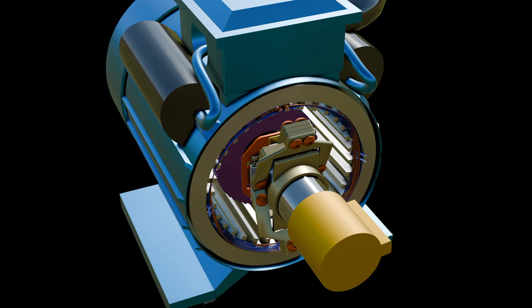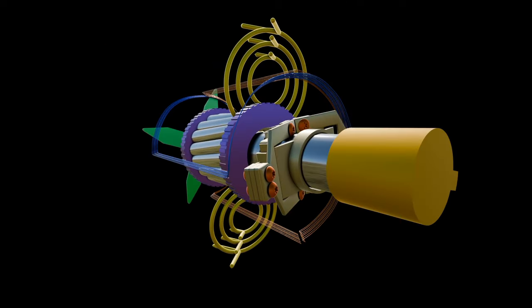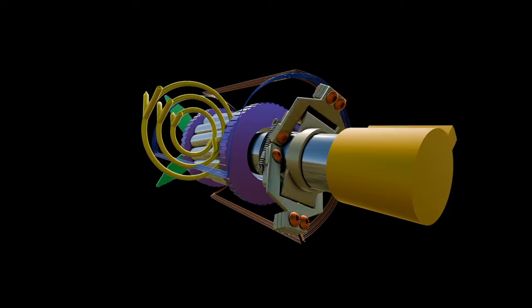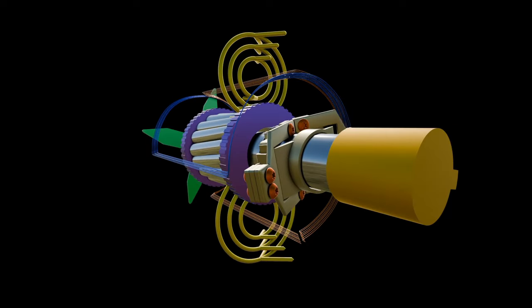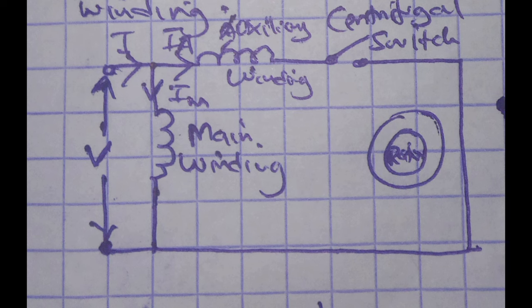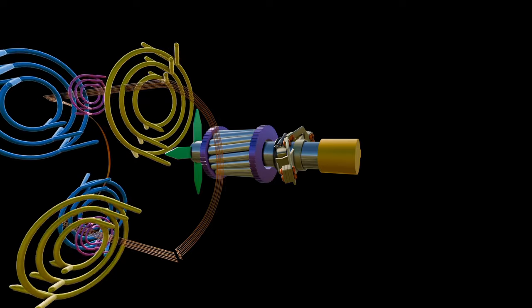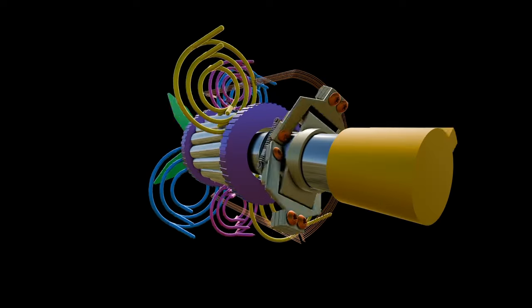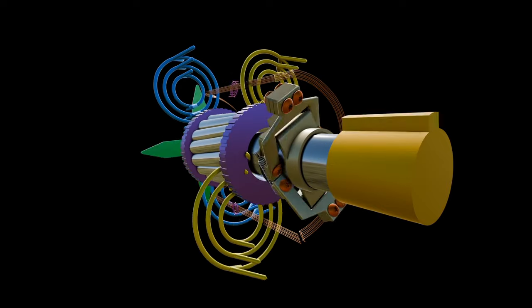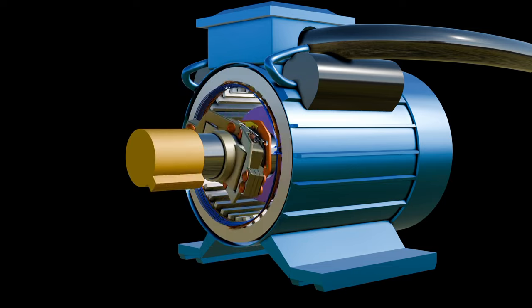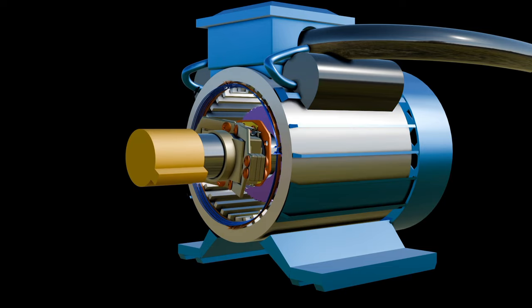Hence, the starting torque of this motor is poor. So, this motor is used in low starting torque appliances like a fan, blower, grinder, pumps, etc. Centrifugal switches are connected in series with auxiliary winding. Auxiliary windings are only used to start the motor. This winding is not useful in running condition. When the rotor reaches 75-80% of its synchronous speed, the centrifugal switch opens. So, the auxiliary winding is out from the circuit. And the motor runs on only main winding.